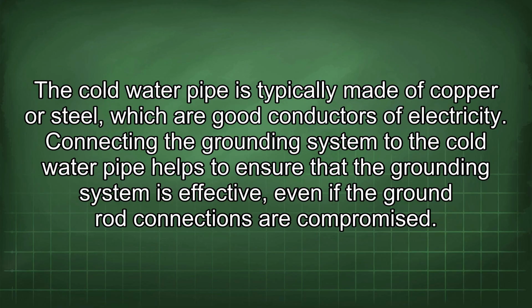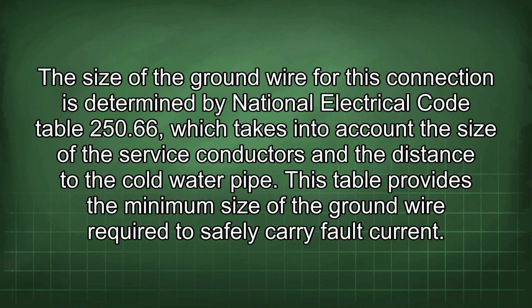Connecting the grounding system to the cold water pipe helps to ensure that the grounding system is effective, even if the ground rod connections are compromised. The size of the ground wire for this connection is determined by National Electrical Code Table 250.66, which takes into account the size of the service conductors and the distance to the cold water pipe. This table provides the minimum size of the ground wire required to safely carry fault current.